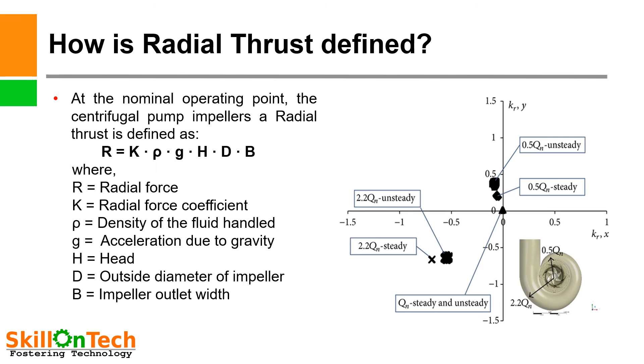How is radial thrust defined? You can see a picture of a volute casing in this slide. As we know, in a volute casing the area of the discharge path is not uniform. Hence, due to pressure variation in the discharge path, a radial thrust is produced.